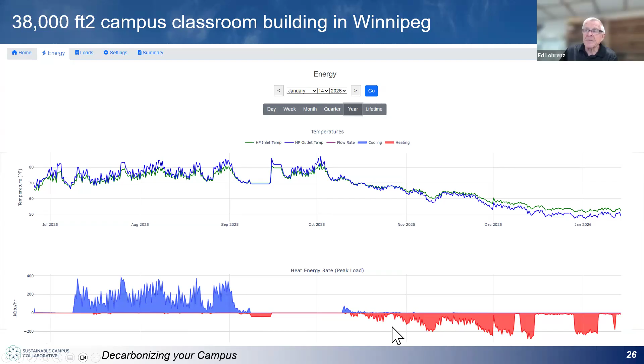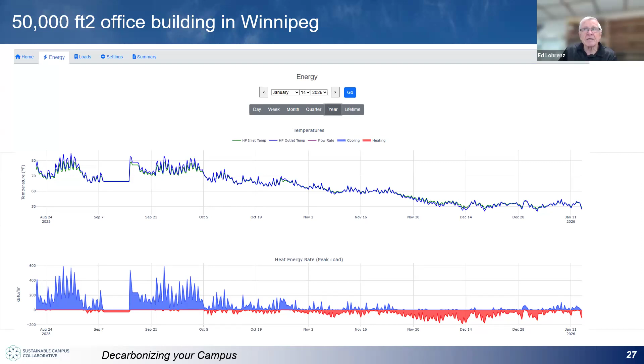This is about a 50,000 square foot office building in Winnipeg. There are times when there's heating going on and cooling going on simultaneously, like in November, December, even January. This is a very good example - the system dropped down to about 45 or 50 degrees Fahrenheit and got up to about 85 degrees last summer. So if we see the temperature getting too high or too cold, you've got a lot of advance warning, because you're working with so much massive dirt, you can see well ahead of time. You can see that train coming a long ways away, and you can react or work proactively to address that potential problem.